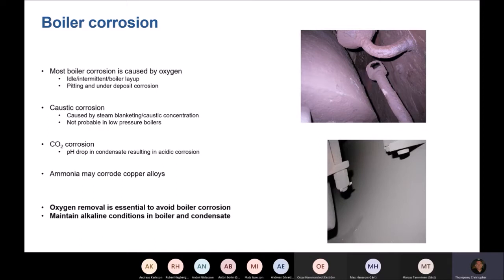If you're going to leave an engine or boiler system unprotected for a long time, as with a lot of these vessels which are just anchored around the world, they should either empty the boiler or fill it 100% up with chemical and water. Have you ever heard of wet layups and dry layups before? Yeah.